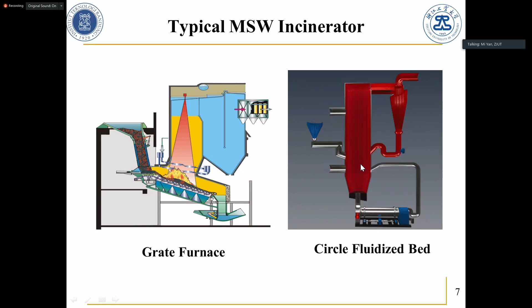So this is the mechanism of the CFB: this is the secondary air, the primary air, and the cyclone. The ash and particles come back through the cyclone, so the sand comes back, and the bed stays very hot. So when your low heating value MSW drops down, it can be heated by the sand, then combust. This is more helpful to ignite the low or worse quality MSW. So this is my answer to your question.